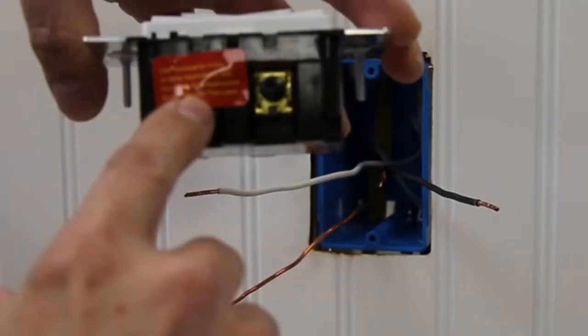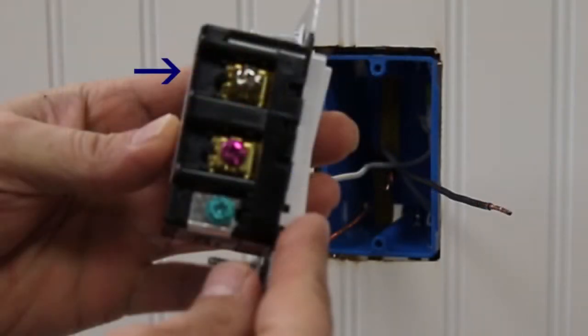Before wiring, it's important you identify the terminal screws on the device to ensure that you're wiring it correctly. The black, or BK, is for the line or hot wire. The silver, or WH terminal, is for the neutral wire. The red, or RD terminal, is for the load. And the green terminal is for the ground wire.